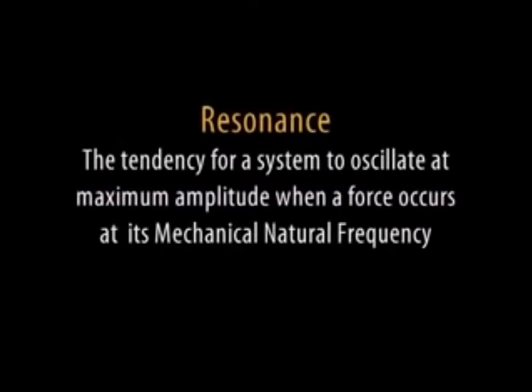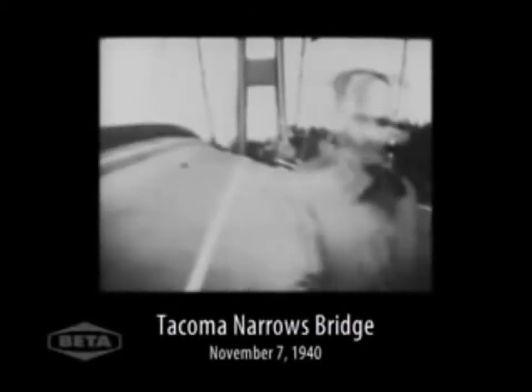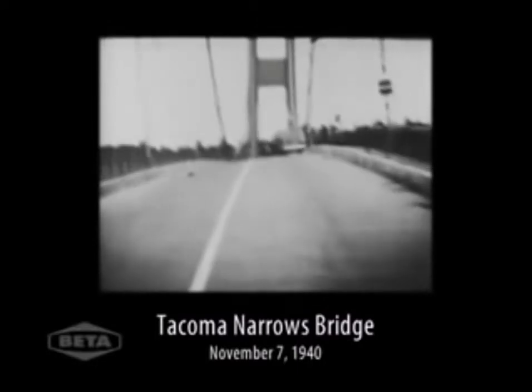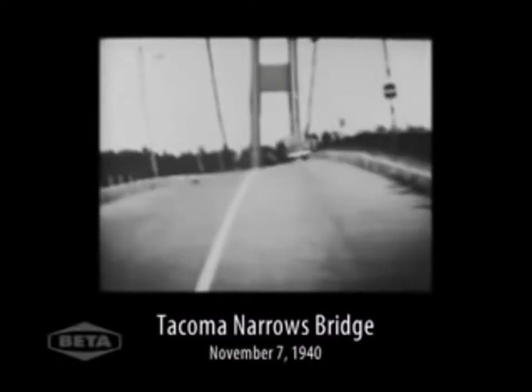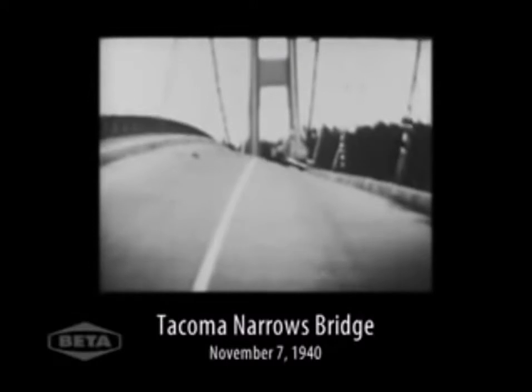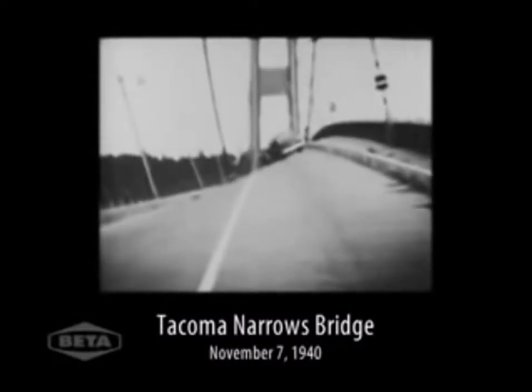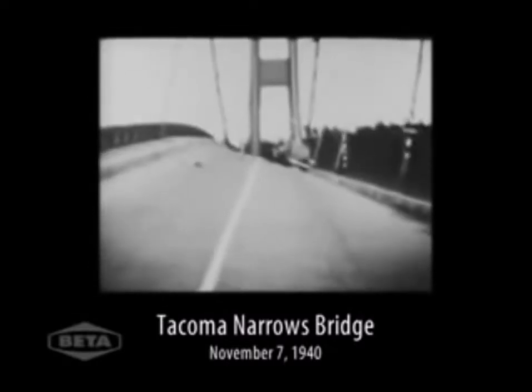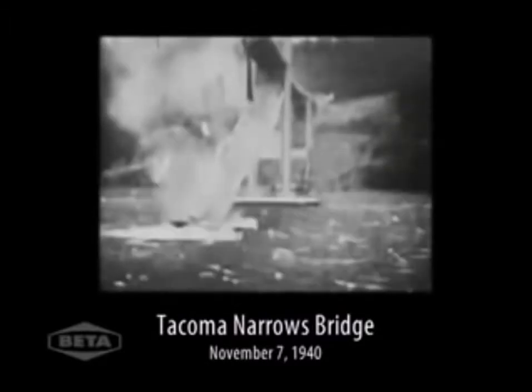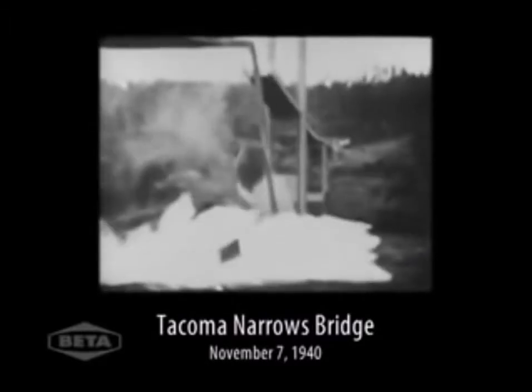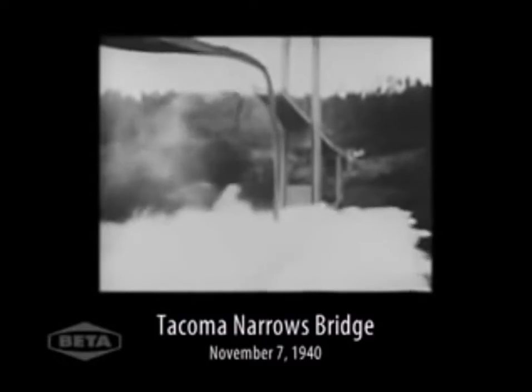Resonance is an important term related to MNFs. A system is said to achieve resonance when a force occurs at the mechanical natural frequency. At resonance, the effect of a force is typically amplified by 20 to 50 times, creating excessive vibration. This explains why some structures fail.